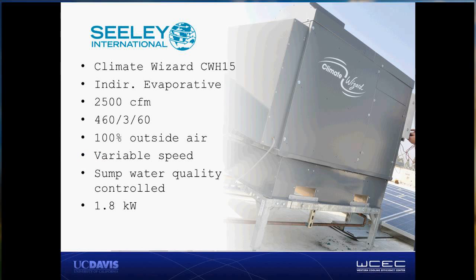The Climate Wizard system is the second piece of equipment we installed. It's very similar in many respects. It's a little bit larger, a 2,500 CFM indirect evaporative system. So in this like-for-like comparison, we were able to install one Climate Wizard and compare that almost directly to two of the Colorados.